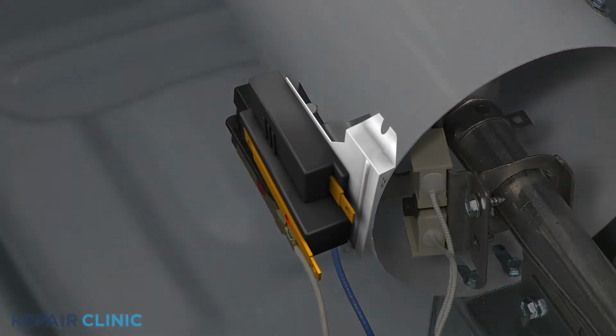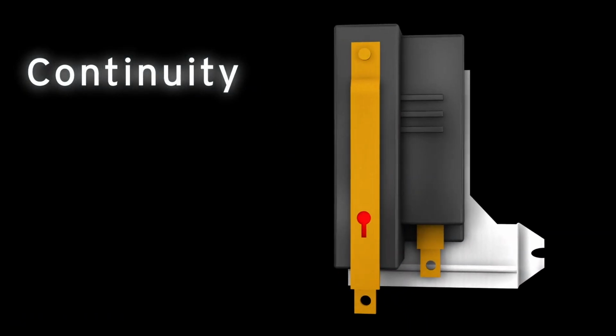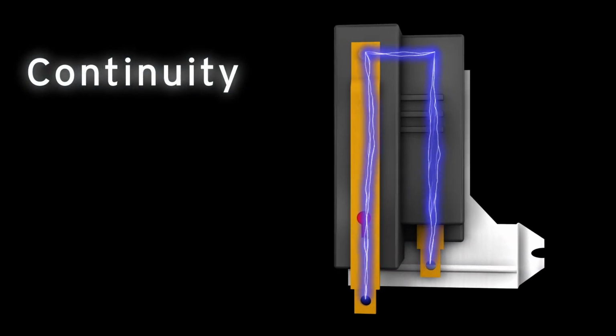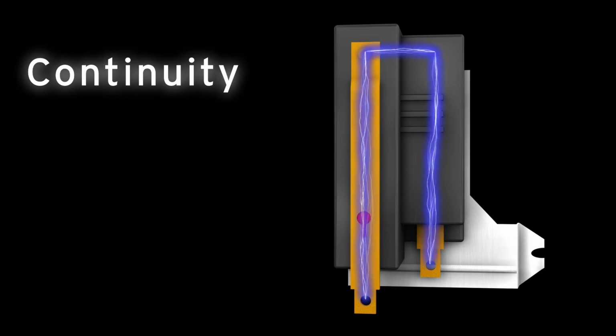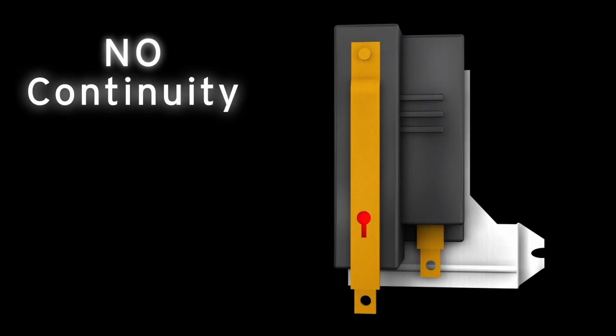continuity. A continuity test will determine if a continuous electrical path is present in the sensor. If the sensor has continuity, it should be functioning properly. No continuity means the electrical path is broken and the sensor has failed.